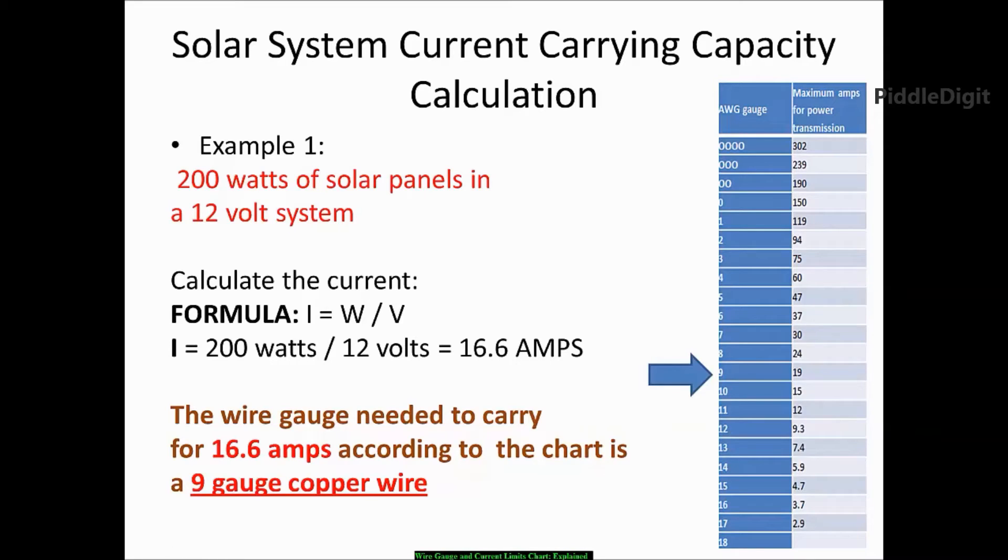Now if you look at the wire gauge and current limit chart, 16 is not on this chart. There is 15 and of course there is 19. The value on this side is the current. So after I've calculated the current here, I reference the chart to see what gauge wire falls in the range of the calculated current. Because 16.6 is not on this chart, I see 15 and I see 19, so I'm going to round up.